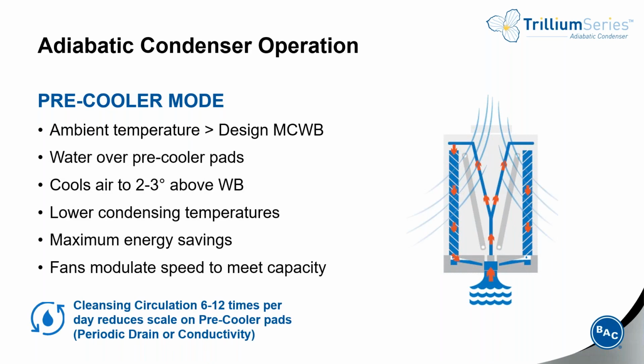As ambient air temperatures rise, once it meets the design mean coincident wet bulb, then pre-cooler mode is activated. Water is distributed over the pad media, and the adiabatic cooling process takes effect. As air is pulled across the pads, it is typically cooled to within about 2 to 3 degrees of the wet bulb temperature. This allows for lower condensing temperatures, maximum compressor energy savings, and the fans, again, will continue to modulate to meet the capacity based on the load and the ambient conditions. Water in the recirculating system is drained periodically and made up with fresh water to maintain water quality.